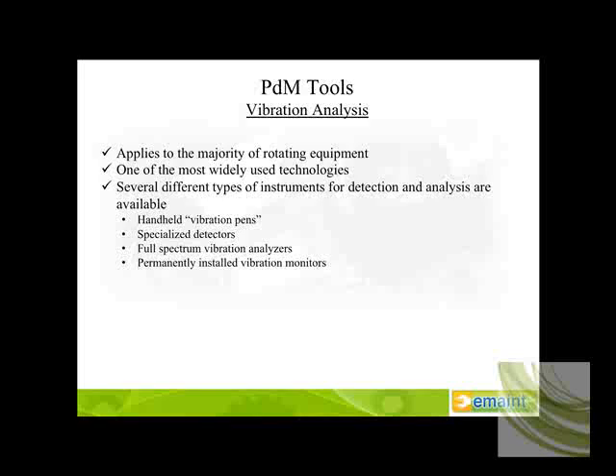Now, while vibration pens may seem from the outset to be the way to go to stick in your toolbox, there's definitely some pros and cons to both vibration pens and full spectrum analyzers. From a vibration pen standpoint, they're certainly low cost, compact, and easy to use, and you can compare measurements to established standards or known standards for those individual assets or components within them. And some models have the capability of integrating temperature measurement as a spot temperature. A couple of the cons with the vibration pen certainly would be limited analysis capability, limited adjustability when you're looking at various spectrums and frequencies, and the trending using a vibration pen must be done manually. There's no software capability with a vibration pen.